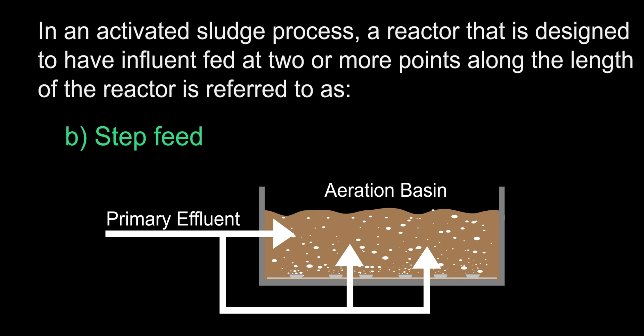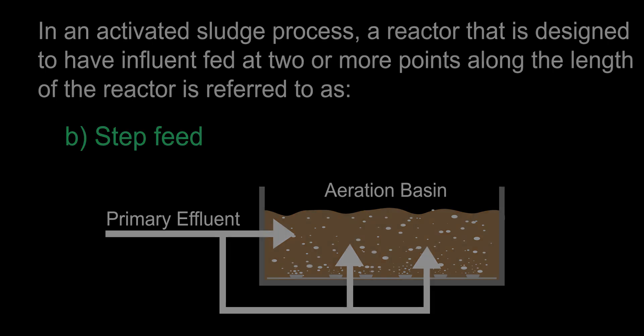The step feed configuration is very useful because it allows the operator to choose how they will distribute the influent going into an aeration basin in steps. This is particularly beneficial when dealing with shock loads. By distributing the shock load across the aeration basin, you minimize any decreases in dissolved oxygen concentration along the length of the basin.